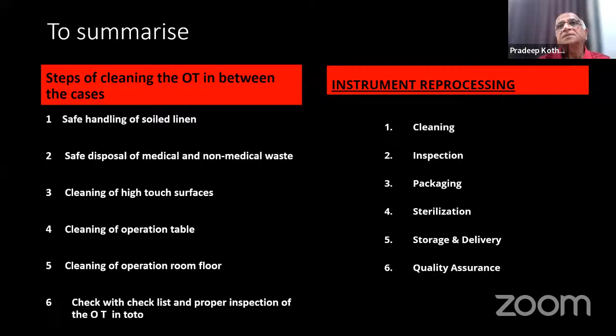High pressure steam sterilization is the best method of sterilization as of today. There are certain ways, like ETO sterilization, which we do. We sometimes do flash sterilization. Storage should be in a proper place and delivery should be done in a proper way. Once any set, drum or tray is opened, it is unsterile. You have to sterilize it again. And we must have indicators inside and outside for quality control.